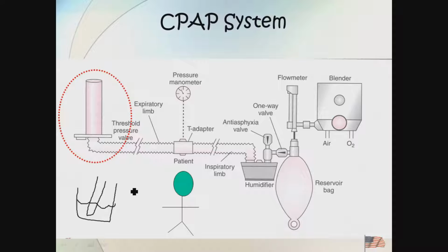Now, obviously that's not a very clean system because you can knock over the water and I lost my CPAP. So there's different ways that we can end up doing that mechanically, through springs, through weighted balls, through all kinds of different things. Okay. I believe Mary talks about the CPAP flow generator, and when she gets to that, it'll make a little more sense. Consider that just a magical black box that creates the desired amount of CPAP. Got a gist of what the system looks like? It's kind of like you're sitting there bored one afternoon with nothing better to do, putting it together. Now, I will tell you that there are machines that will do this automatically, a whole lot easier. But if push came to shove and you had to put it together yourself, it's kind of what you've been used to seeing so far with the high-flow nasal cannula system, just adding a couple other pieces in there.